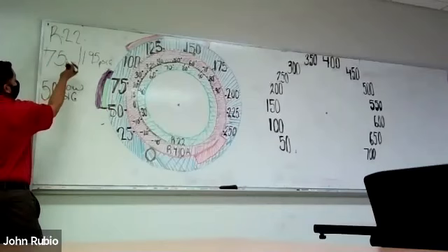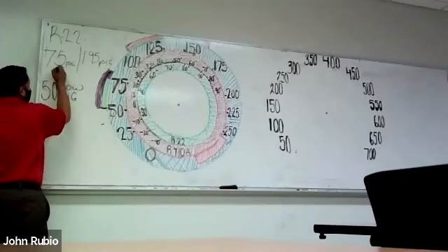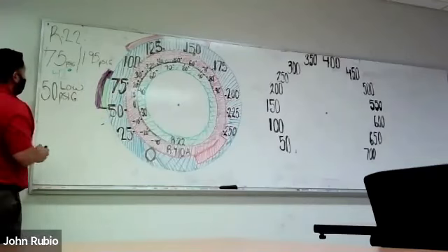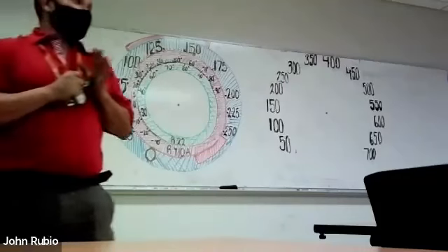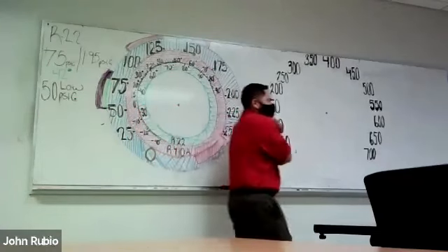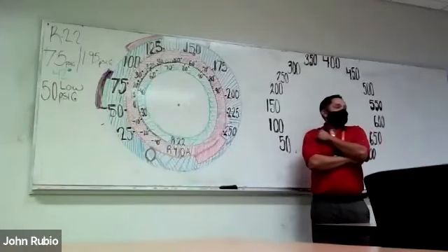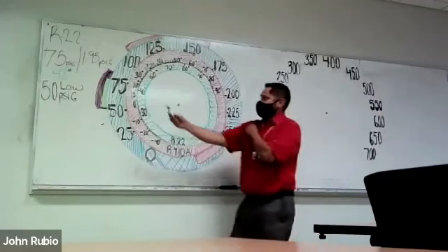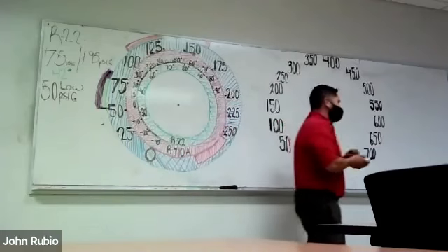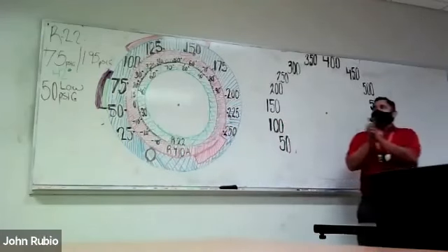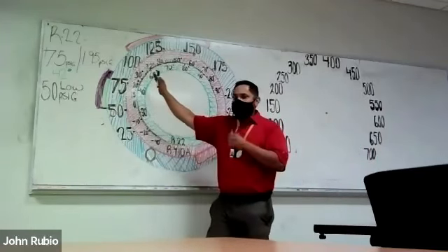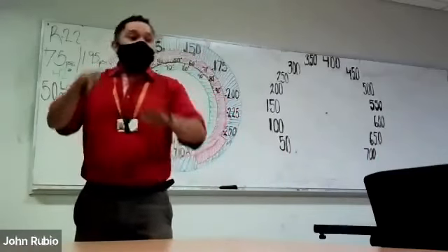When you say 75 PSIG, you put a slash. So look at that reading. All I did was write the PSIG and the corresponding temperature next to it. That indicates to anyone reading this that I'm not just looking for gauge pressure. I'm anticipating that I do need this temperature. I need the temperature so I can calculate the superheat and subcool. We're not going to get into superheat and subcool until we understand the very purpose of the gauge is to give us the first number we need. The corresponding temperature of the evaporator coil to where the pressures are.